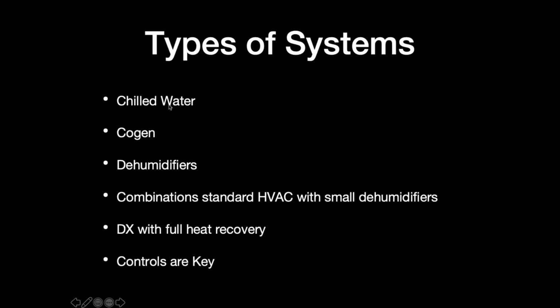The type of systems that we've seen applied in grow facilities, in the grow rooms, those 4 grow rooms that I was talking about, we're seeing people use chilled water. We're seeing cogen also. Because the energy demand is so high in these facilities, a lot of people are installing cogen facilities to supplement the energy that they can get from their providers. In most cases, we're also seeing dehumidifiers being used. Really what you see is a combination of standard HVAC equipment like rooftop equipment, split systems, et cetera. And then you've got small dehumidifiers.